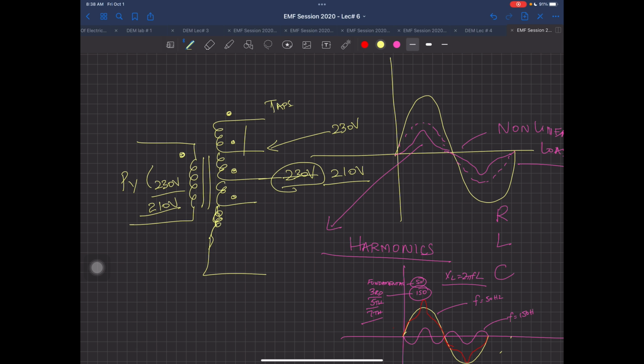Sometimes this 230 can go to 240 volts. When this goes to 240, now it's too much, so you have to reduce it. So you will come down on this tap and you will get 230 volt. So by taps you are changing the turn ratio of your transformer, and this is all being controlled by relays in a transformer.